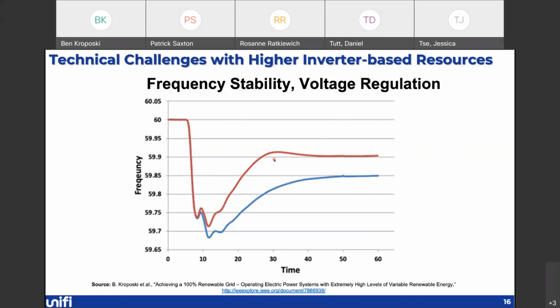Now, historically, I would say before IEEE 1547-2018 came out, the inverters would see this drop, and if it went below the tripping frequency, the inverters would just trip offline. But what we're looking at now is we get higher and higher levels of inverters. We'd like them to stay online and participate in actively keeping the stability of the grid in place. So that's one of the challenges.